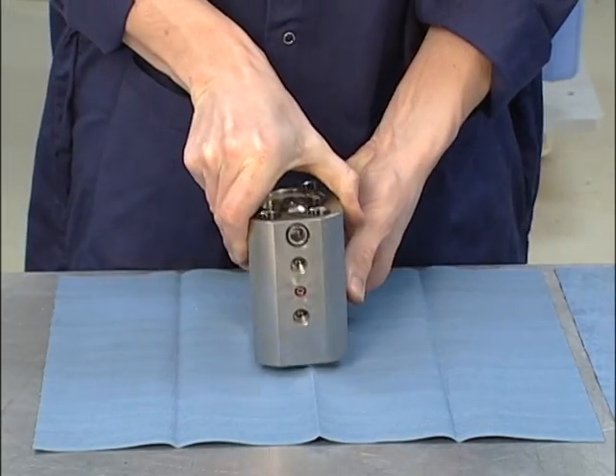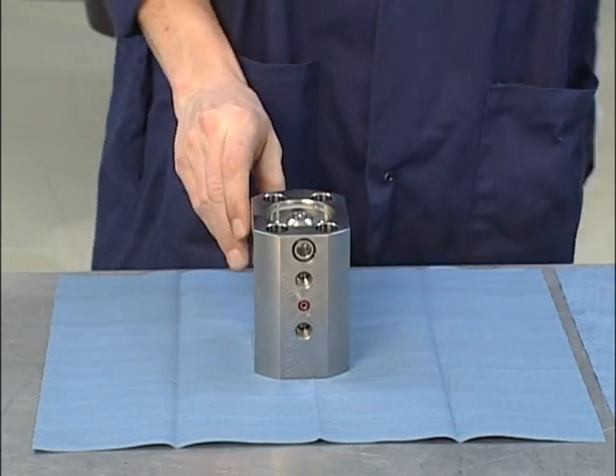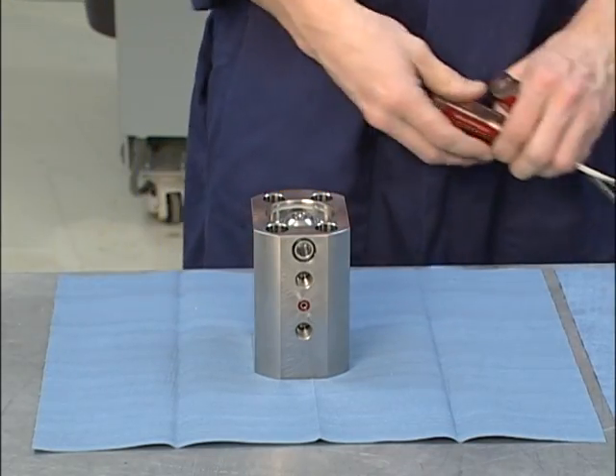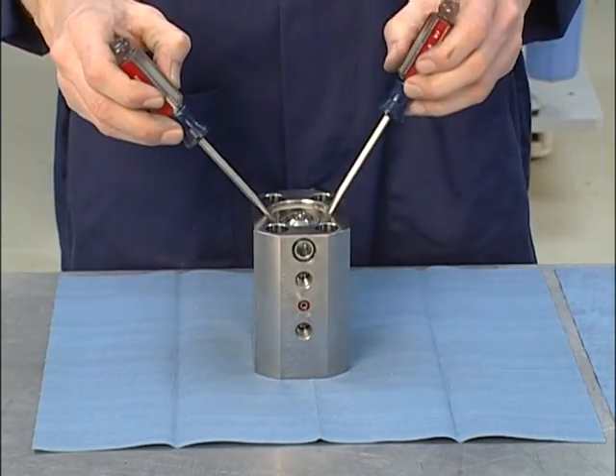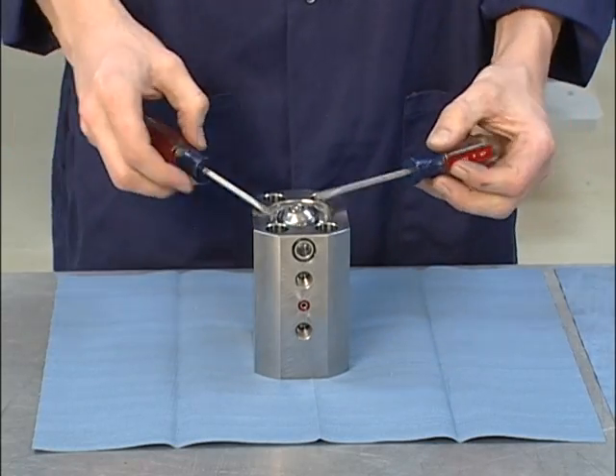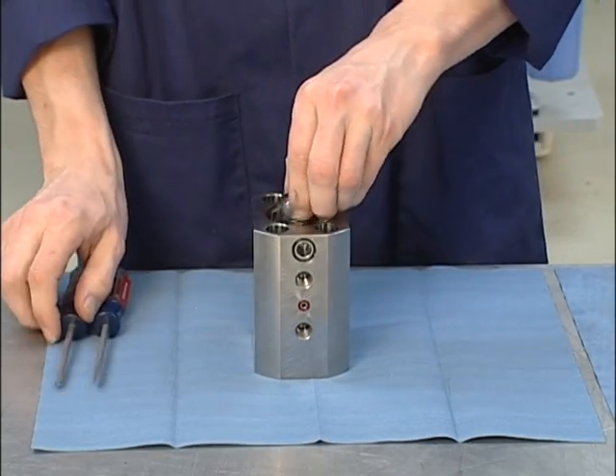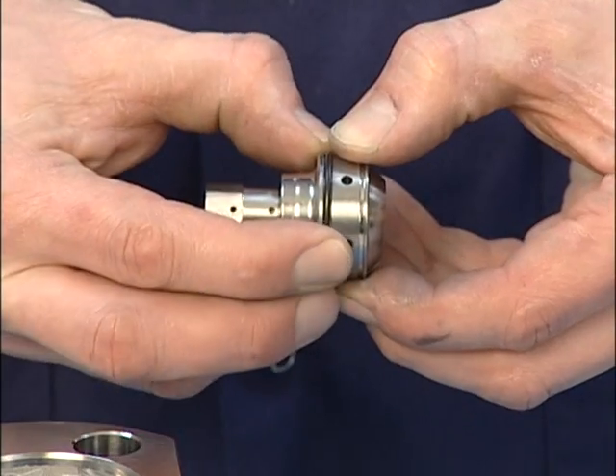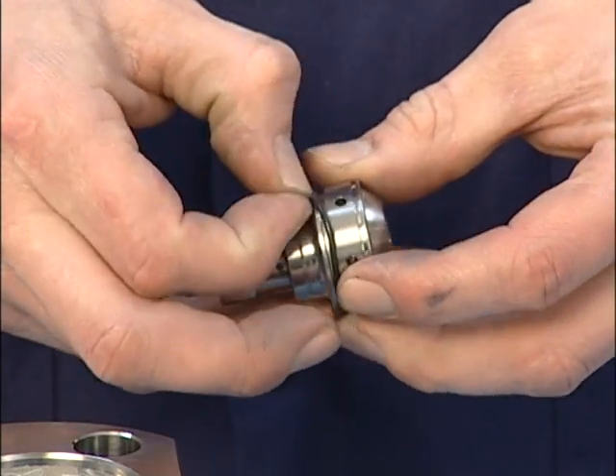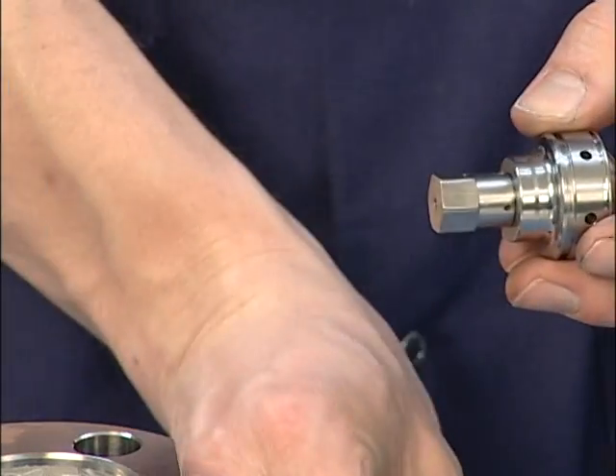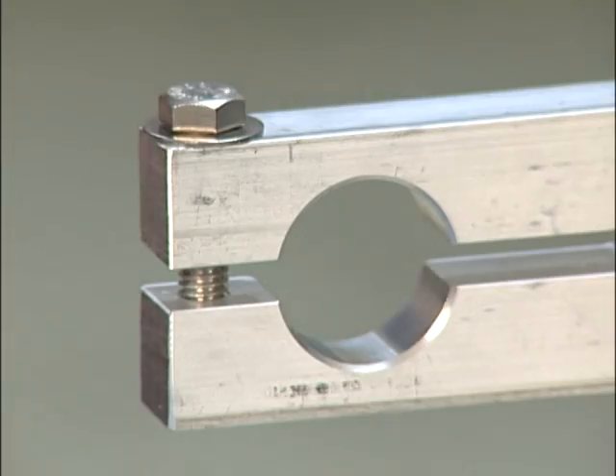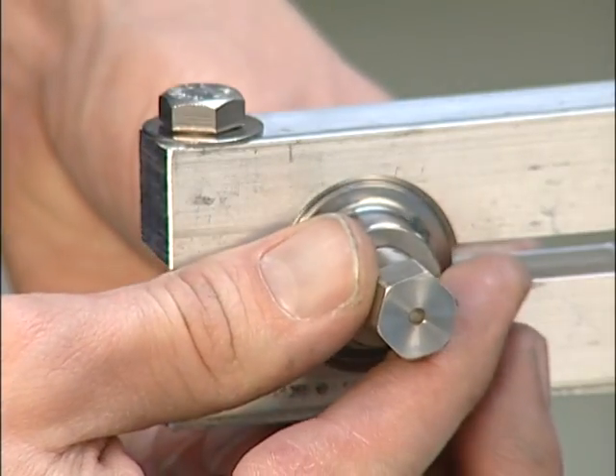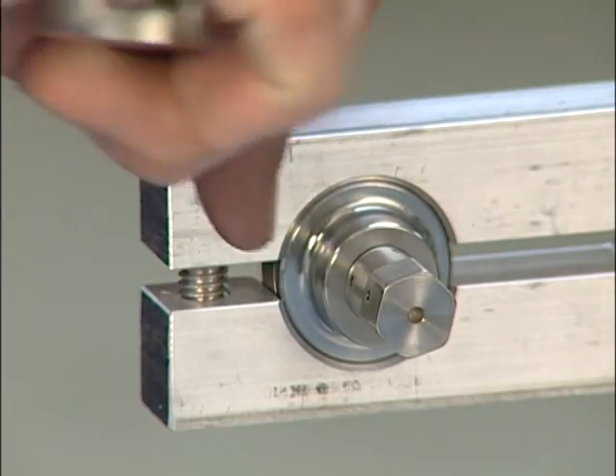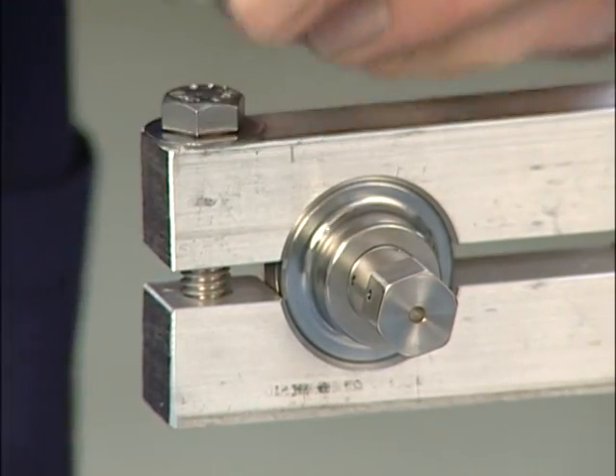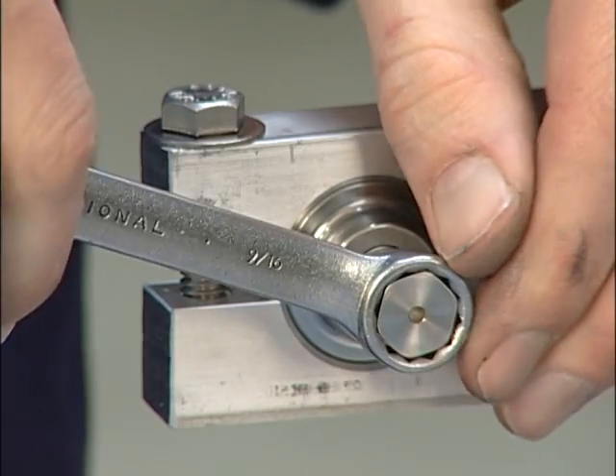On a workbench, remove the check valve from the end cap by placing the tips of 2 small screwdrivers in the grooves provided on the check valve. Remove the O-ring from the outside of the check valve and place the check valve assembly in the flow check valve fixture with the outlet cage exposed. Remove the cage.